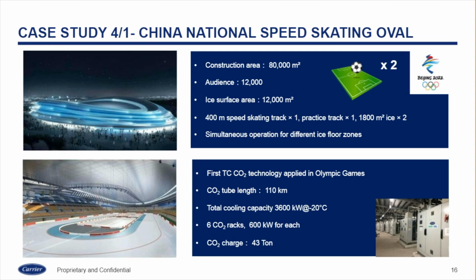The ice surface is around 12,000 square meters, which is the largest in the Asia region so far. It has a 400-meter speed skating track, and also two ice rinks of about 1,800 square meters. Also, this is the first CO2 transcritical technology for direct cooling applied in the Olympic Games. We have had some CO2 applications in South Korea, Foshan, and Sochi in Russia, but this is the first transcritical CO2 technology application for the Olympic Games.